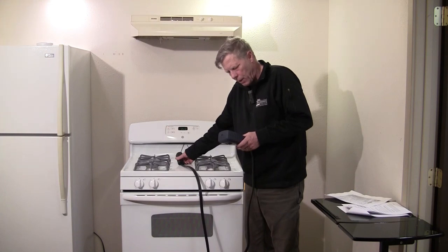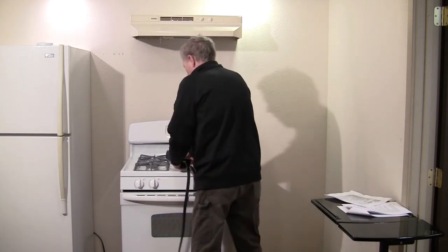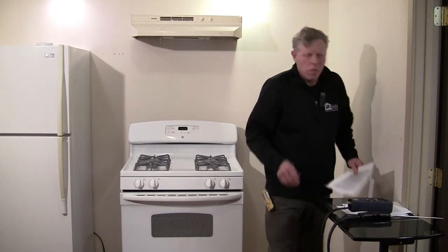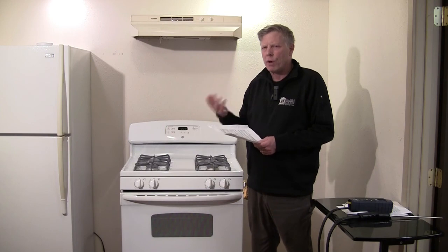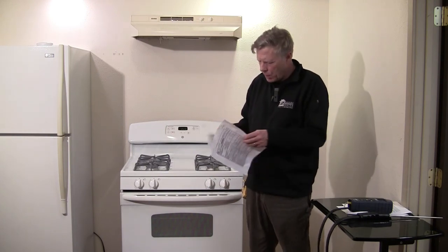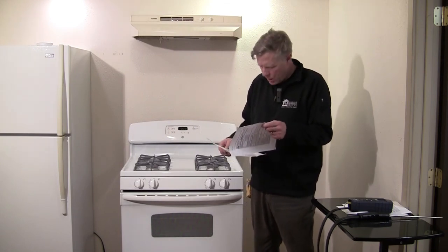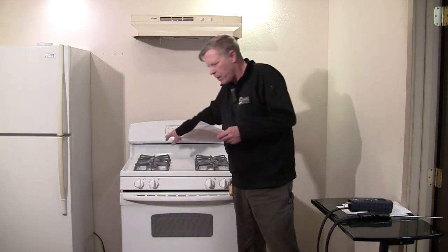Okay, it looks like it's leveled off at about 270 parts per million. All right, 270, take it out of there. 270 is a fail. We need to be at about 225 parts per million. And so that would be an unacceptable measurement, and we'd have to have someone come address that high level of CO. Go ahead and turn this off.